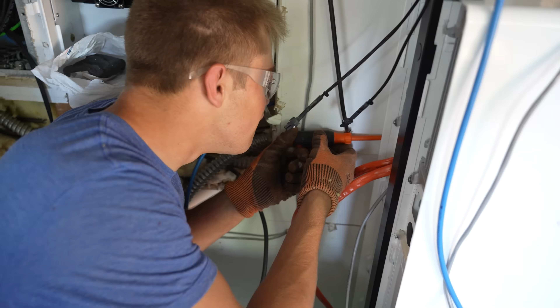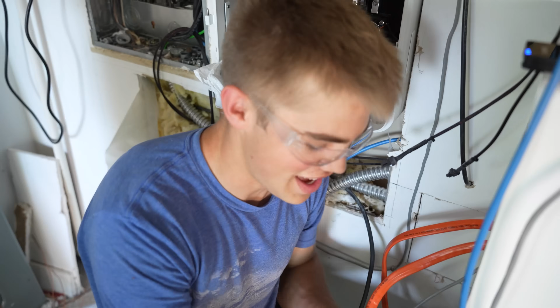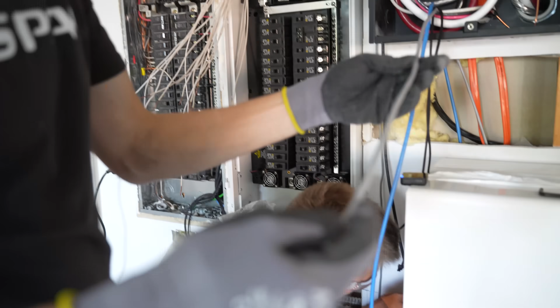What gauge wire are you using? 10 gauge wire for all power walls, across the board. What kind of communication wire is in there? Is that 16/4? 16/4 with the drain wire, shielded. Do you know what the shielding's for? Because we're running it with the higher voltage wires. Right, so the class 3 wire is rated for 300 volts or more. Class 3 wire, so that's important.